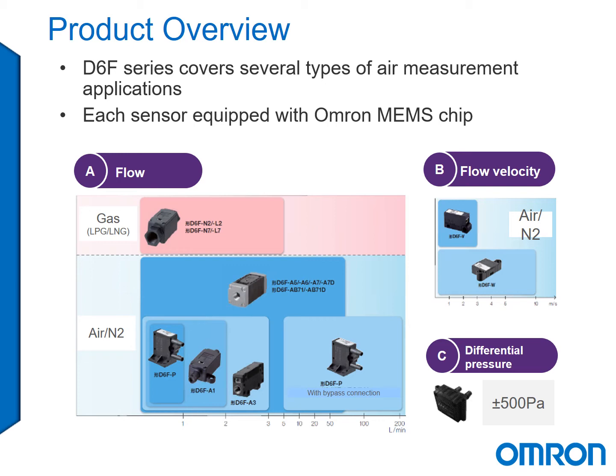Airflow velocity sensors measure air velocity as it passes over the sensor, versus airflow sensors which have air running directly through the sensor. The airflow velocity sensor is designed to be mounted in open air applications. We also offer the differential pressure sensor, measuring plus or minus 500 pascals. These sensors, while not directly related to airflow, can be used in various airflow applications, such as a ventilator.